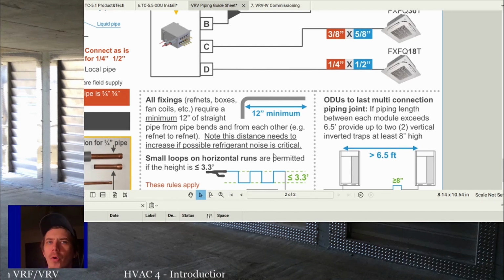And if you can go farther, go farther. Typically you're not going to run into a ton of situations where you need to split, then split, then split. But when you do, try and put as much difference between those as possible, as much space. And then if you have to loop back to your last unit, it's probably no big deal. As long as you're following the piping length requirements, you'll be okay. We'll look at what a layout sheet looks like at some point too.